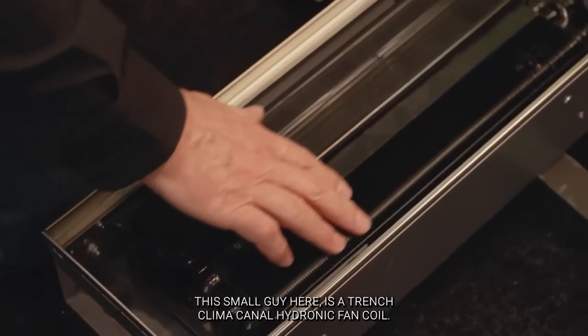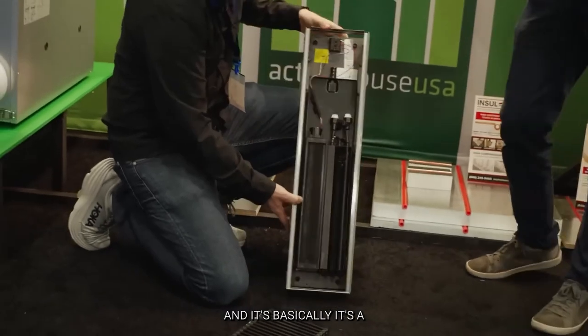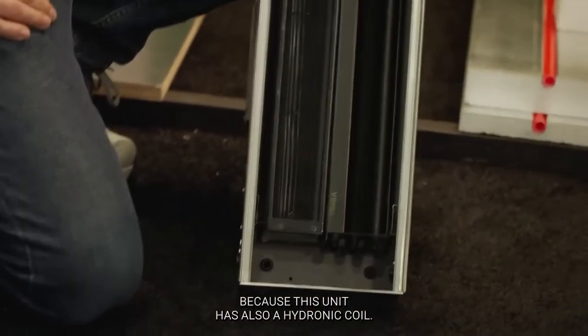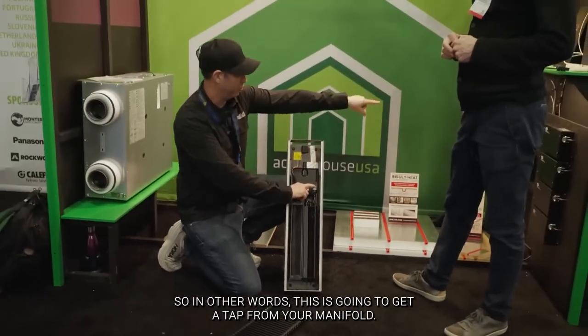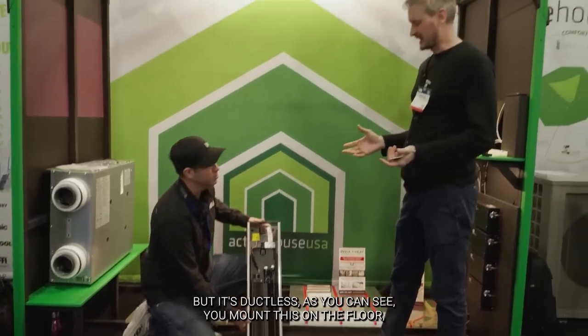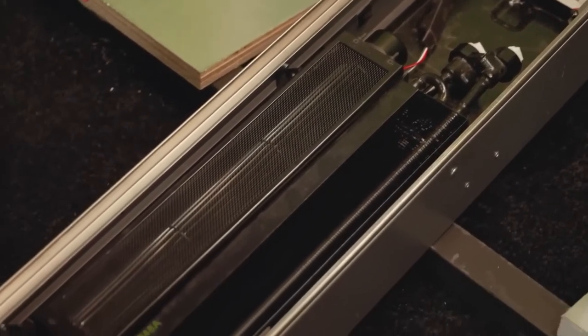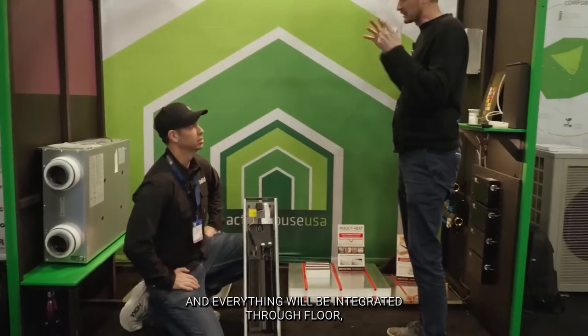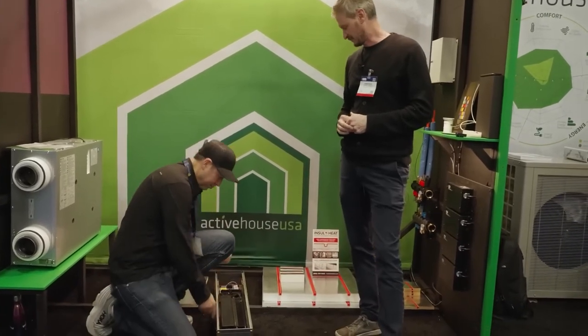This small unit here is a trench Clima Canal hydronic fan coil, manufactured by a Belgian company named Jaga. With this unit we can integrate with the rest of the system because it also has a hydronic coil. It gets a half-inch tap from the manifold — chilled water goes in and the coil gets cold, just like a standard AC coil, but it's ductless. You can mount it on the floor, ceiling, or wall with no ducts needed. A little squirrel cage fan runs on 24 volts, integrated with radiant floor, ceiling, HRV, and Jaga — a complete HVAC solution for the house.